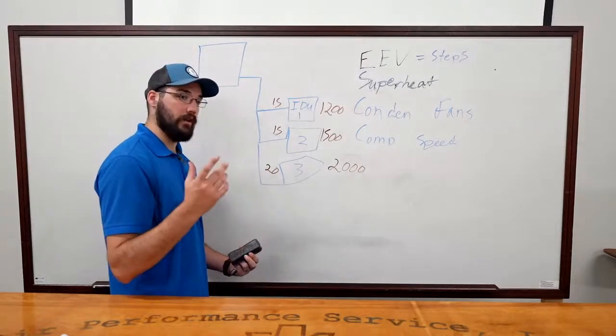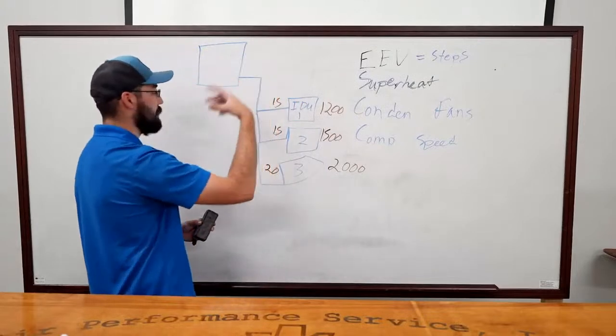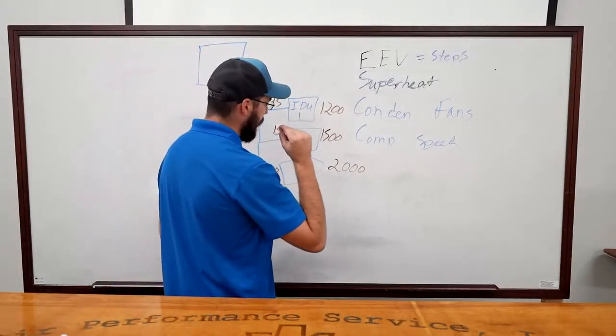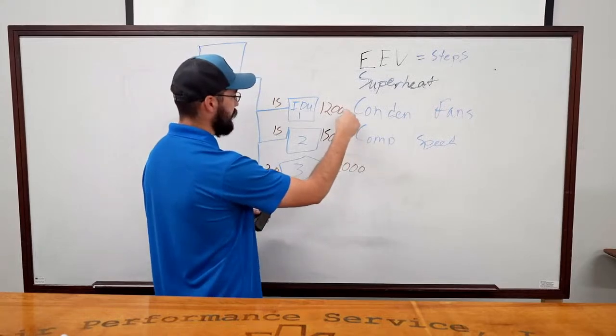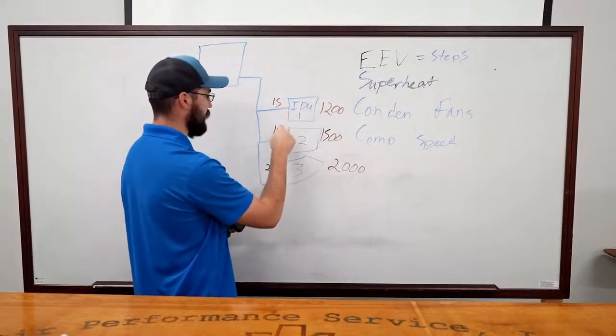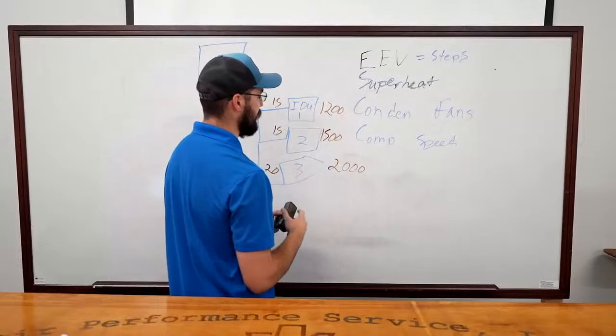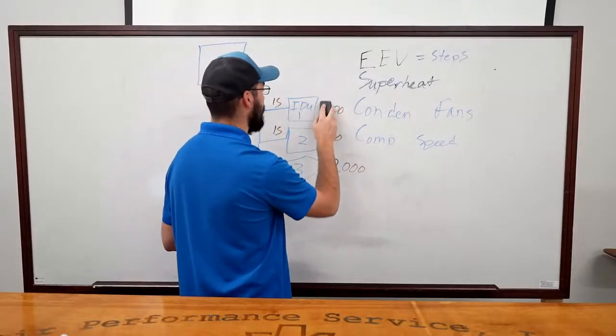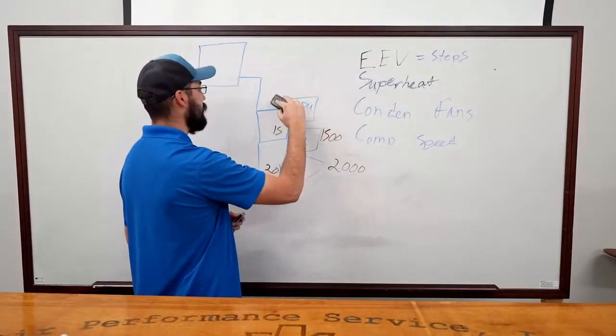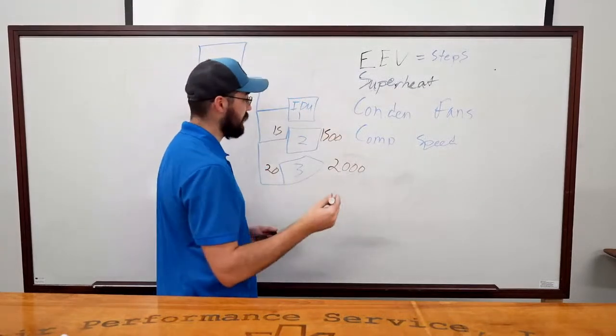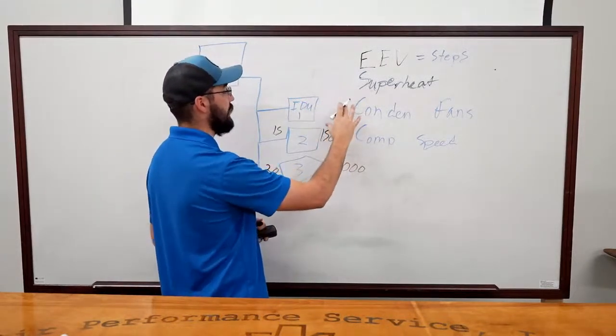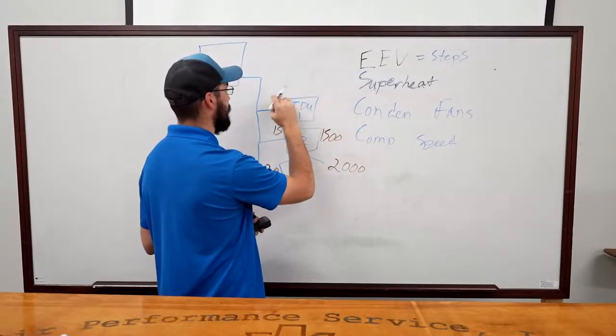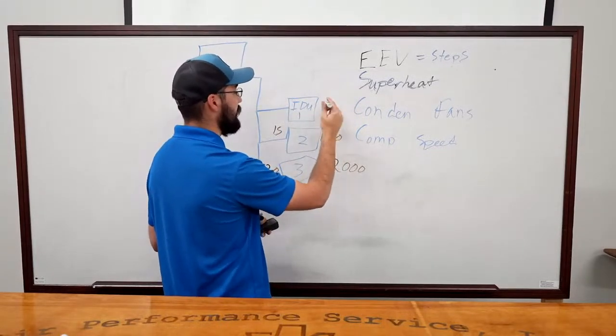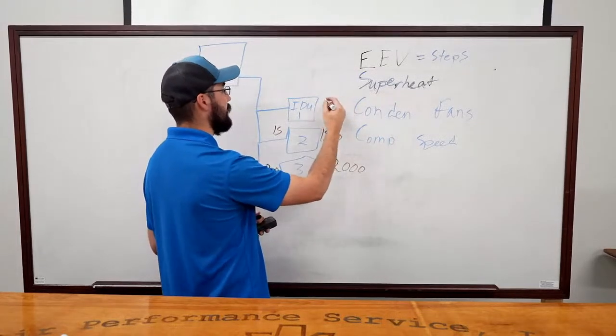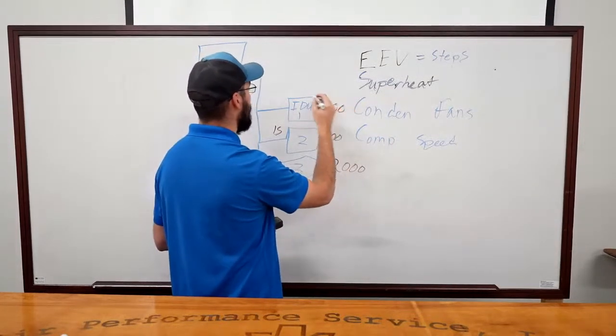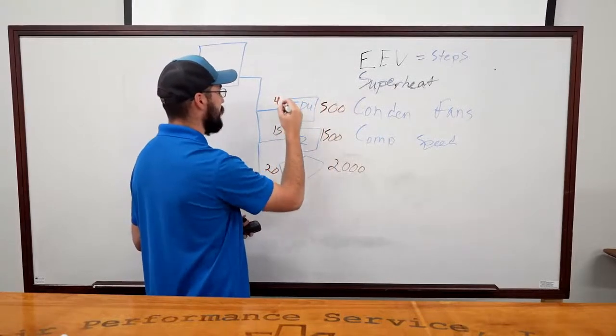A less safe way, which requires a lot of caution, is to charge just like we would charge a split system. What you're watching for is these numbers and these numbers, so your superheats and your steps, to start coming down. And what you'll see is the indoor unit, the first one on the run, will be the first one to reflect the results. So say it's running at 1500. Let's say we got up that high and we had a 20-degree superheat. You'll start to see it come down. It may go to 1000, and it's eventually going to work its way to 500, and it's able to run at 4 degrees of superheat.